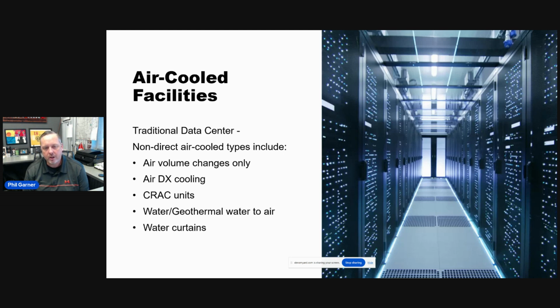There's also water and geothermal with water to air. Instead of DX cooling, where your air goes across a refrigerated coil, your air goes across a heat exchanger that's being cooled by either water or geothermal water. Again, it brings that temperature down, so the delta T goes down and helps cool the facility.